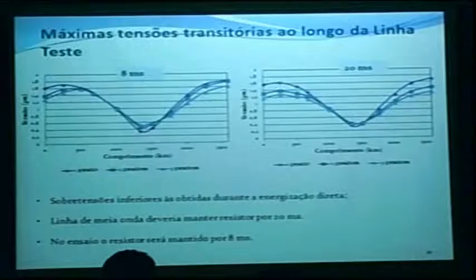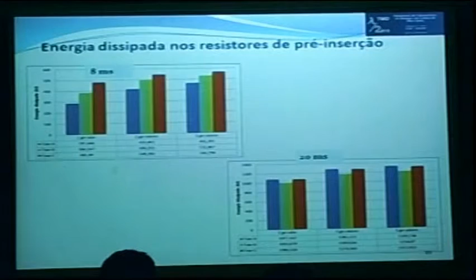In the study, it's not yet defined whether we are going to maintain the resistor or not, but if it is maintained, it's going to be for 8 milliseconds. I do not know, we still have not defined the impact of eliminating the resistor. If it's too complicated, we're going to maintain it. What's important for us is to see the energy that this resistor is going to have to consume throughout the maneuver. Here for 8 milliseconds we have 480 kilojoules, and here we reached 1 megajoule. So in reality this needs to be checked. This is not our case. We are not going to maintain it for 20 milliseconds, and this value of 480 kilojoules is a reasonable value. It's not too high.